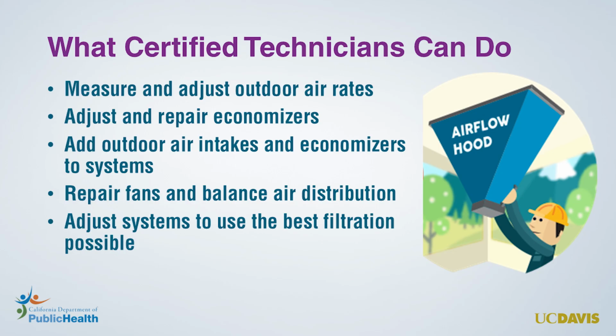Certified technicians can measure and adjust outdoor air rates, adjust and repair economizers, and install new outdoor air intakes and economizers on existing systems. They can repair or replace fans and balance air distribution in buildings. Additionally, they can adjust systems to use the best compatible filtration so you're confident that you're providing the best indoor air quality possible with your existing equipment.